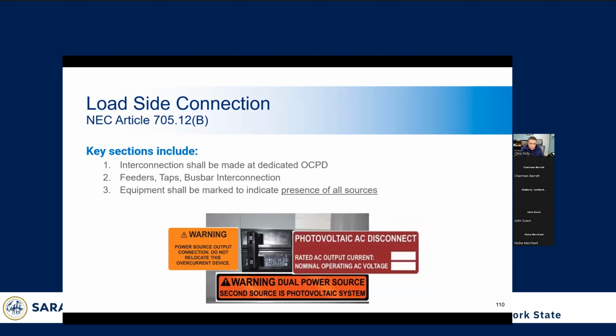All right, so this is a load side connection. This label is required when the 120% rule is used to add additional PV to the bus in excess of its rating. We talked about this for several slides earlier. If you're going to add additional power to the bus, the source of the PV power has to be at the opposite end of the bus, so that it doesn't overload the bus, as we've seen already. This would have to be at the opposite end of the panel from the main breaker. And there are all these labeling requirements for this specific situation.